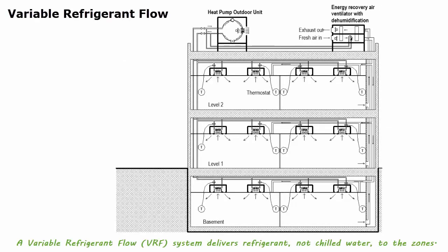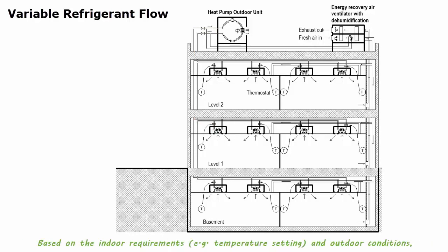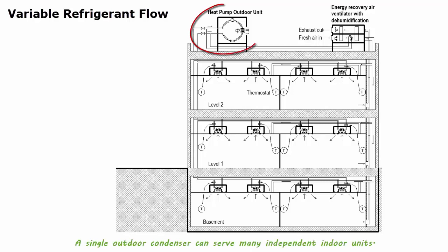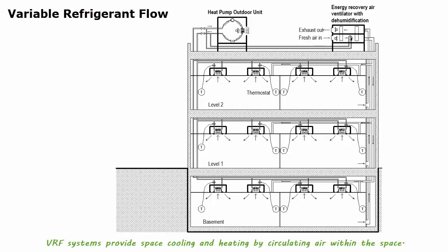A variable refrigerant flow system delivers refrigerant, not chill water, to the zones. Based on the indoor requirements and outdoor conditions, the refrigerant's flow can vary from zone to zone, delivering just the appropriate amount of refrigerant that each zone needs. A single outdoor condenser can serve many independent indoor units. Variable refrigerant flow systems provide space cooling and heating by circulating air within the space.